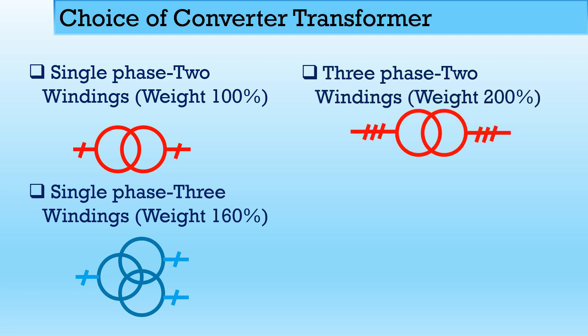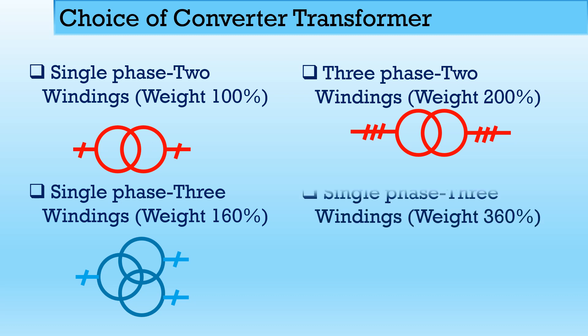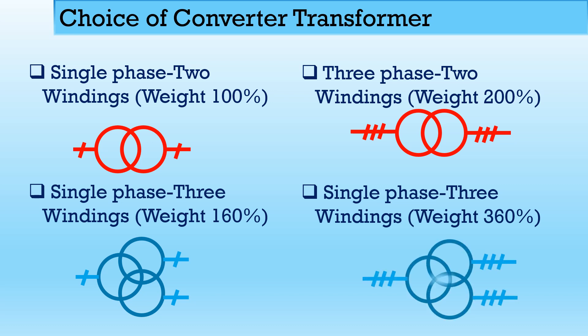The third option is a three-phase two-winding transformer, but its weight will be 200%. In the previous case (single-phase three-winding), the weight is 160% compared to the first case. The fourth option is a three-phase three-winding transformer; taking a single unit, its weight is 360%. It is observed that using the single-phase three-winding transformer at 160% weight is the preferred solution. For a 12-pulse system, you would require six such transformers, whereas twelve transformers would be needed with two-winding units.